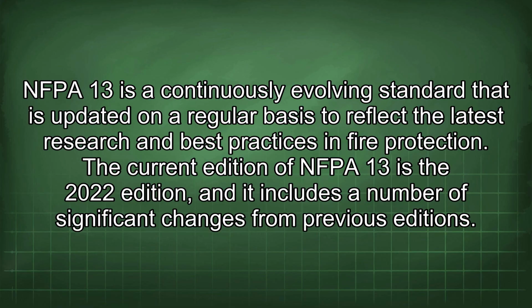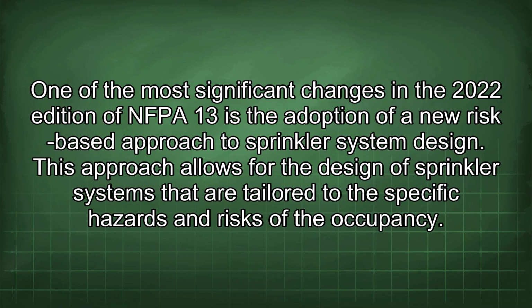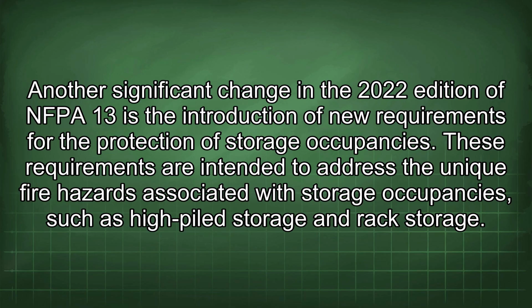The current edition of NFPA 13 is the 2022 edition, and it includes a number of significant changes from previous editions. One of the most significant changes in the 2022 edition of NFPA 13 is the adoption of a new risk-based approach to sprinkler system design. This approach allows for the design of sprinkler systems that are tailored to the specific hazards and risks of the occupancy. Another significant change in the 2022 edition of NFPA 13 is the introduction of new requirements for the protection of storage occupancies.